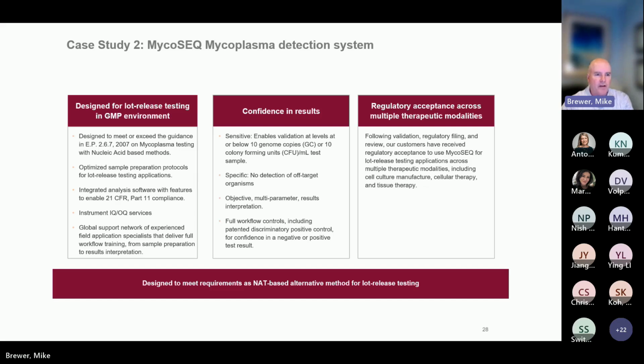It also uses an integrated software analysis platform to enable not only automated positive-negative calls, but also full 21 CFR Part 11 compliance. To fully support our system, we offer instrument validation services, IQ/OQ, and a global support network of experienced field application scientists that can provide full workflow training from sample prep to results interpretation.